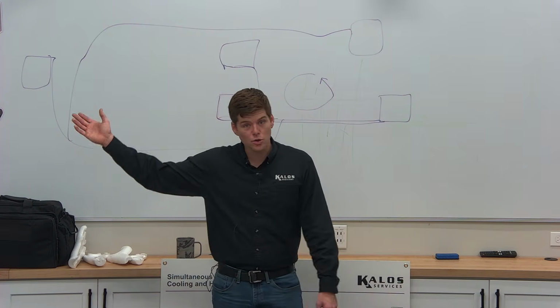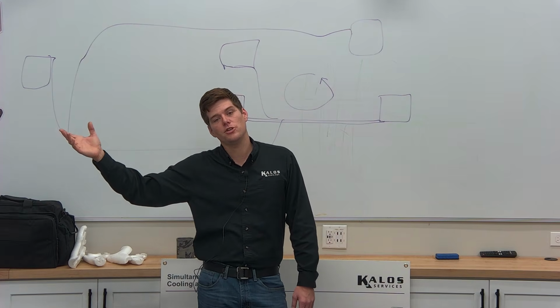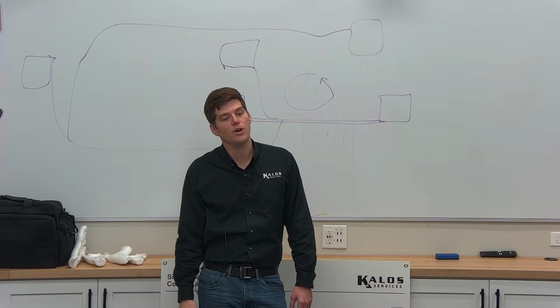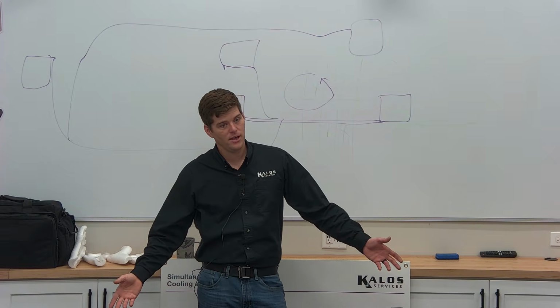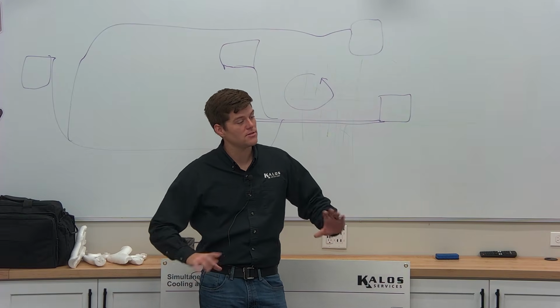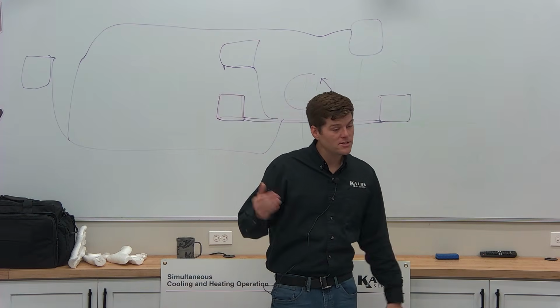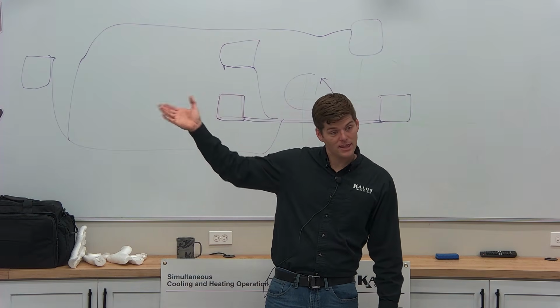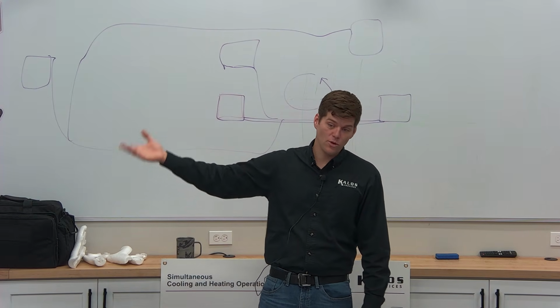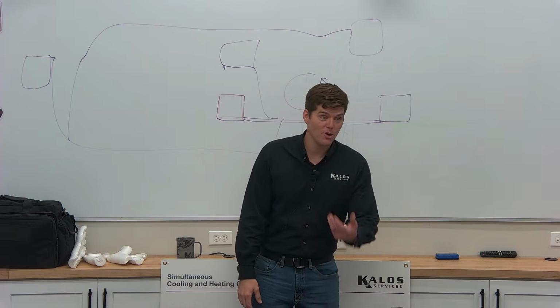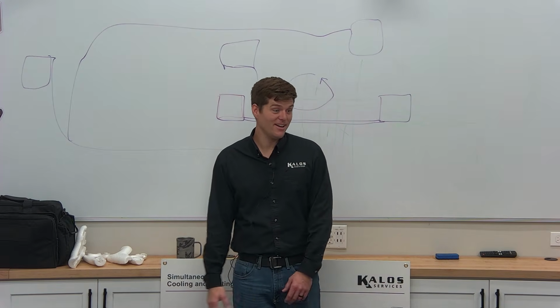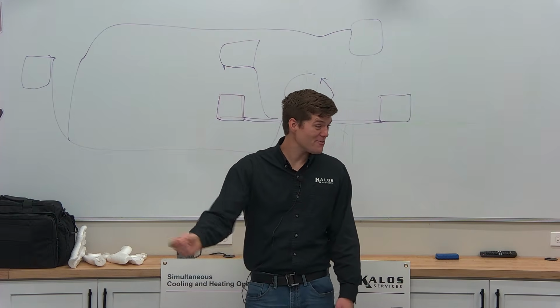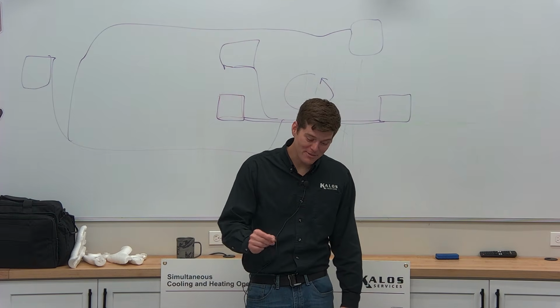So when you break these rules, when you go less than 20 inches, right? There's certain applications where, sure, I could not avoid it. Okay, just don't do it again. Keep an eye on the system, watch it. But when you consistently go out of your way and you do an entire system like this, just go ahead and order the compressors, right? Keep them in your warehouse. Put it on your calendar, 1 year from now: I should probably go change that compressor.